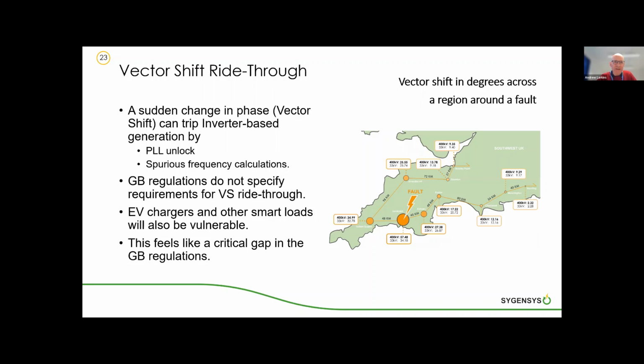Coming closer to home, we said a sudden shift in phase can trip generation either by phase-locked loop unlock or also by spurious frequency calculations. These embedded generators also have high and low frequency protection, and the calculation they use to measure frequency can be fooled by phase jumps. So that can also trigger unexpected tripping. At the moment, the GB regulations for this embedded generation don't specify any requirements for vector shift ride-through. Actually, in the type tests, a test for phase shift is included, but there's no requirement in the regulations to meet that test result.